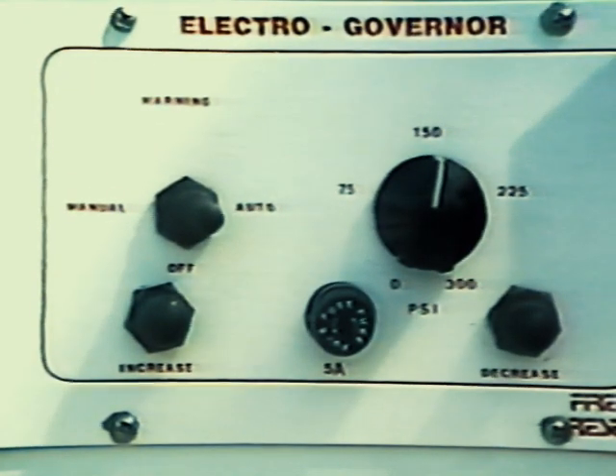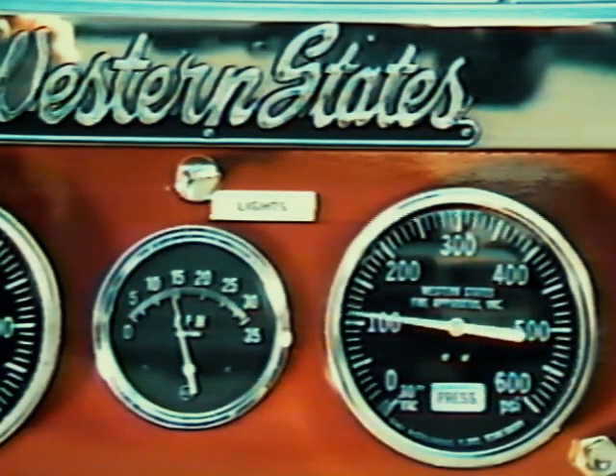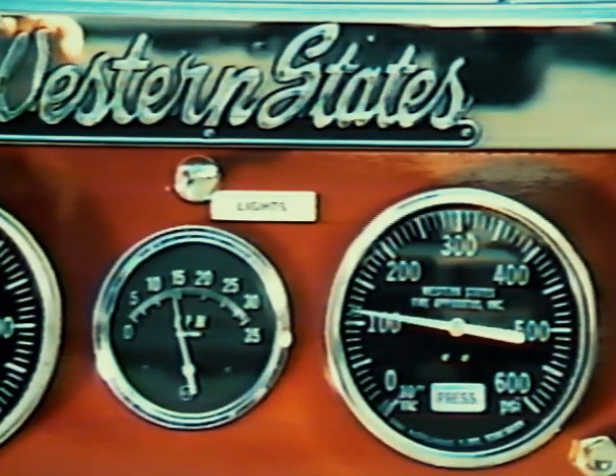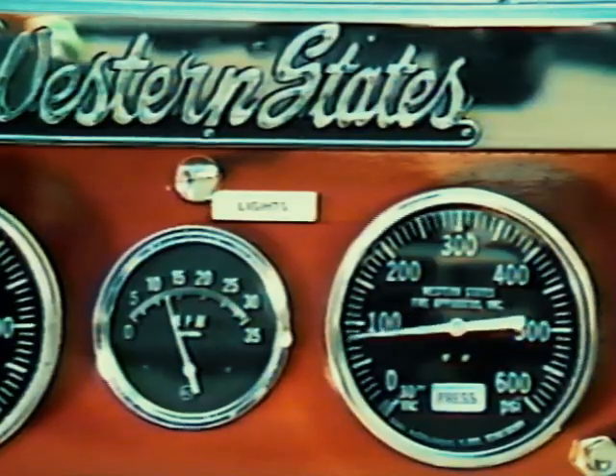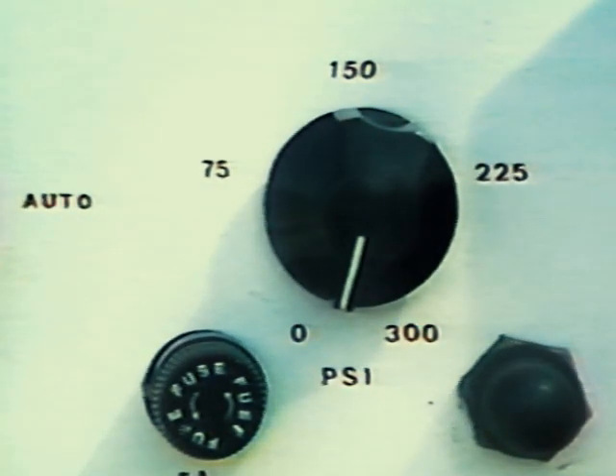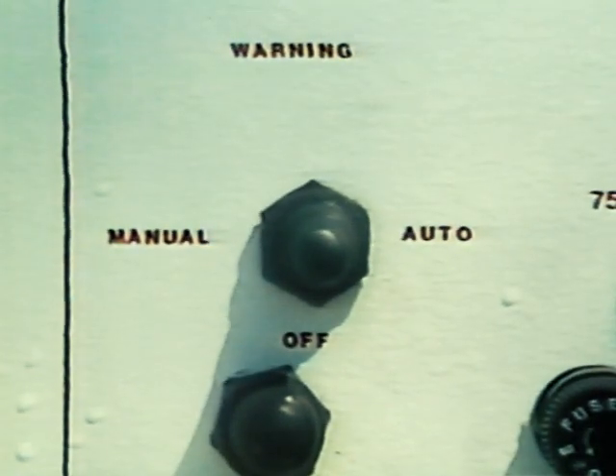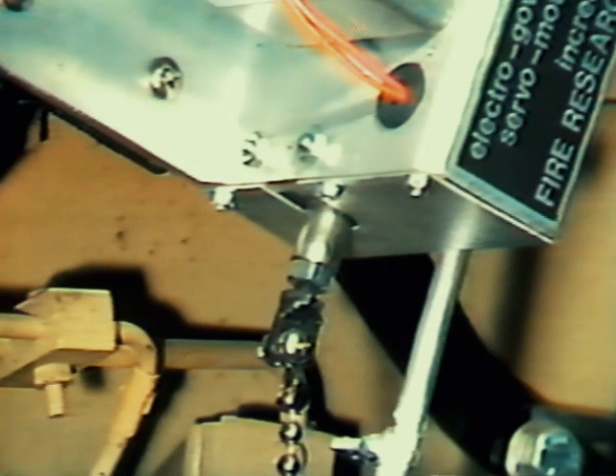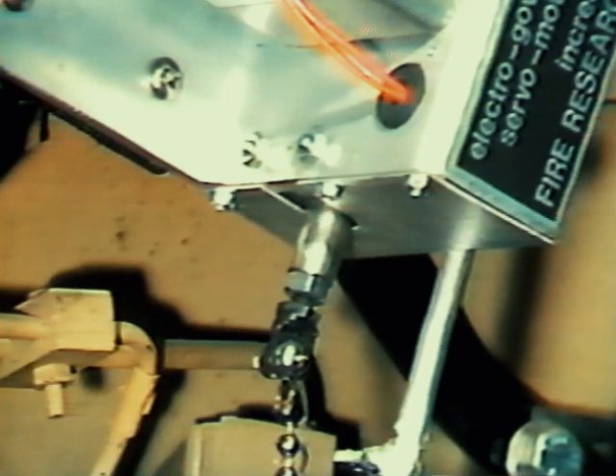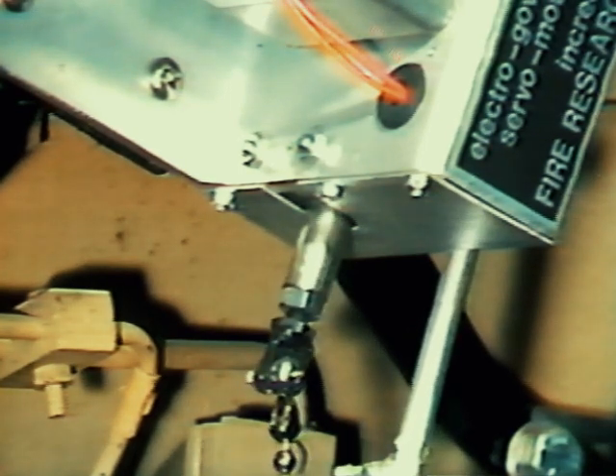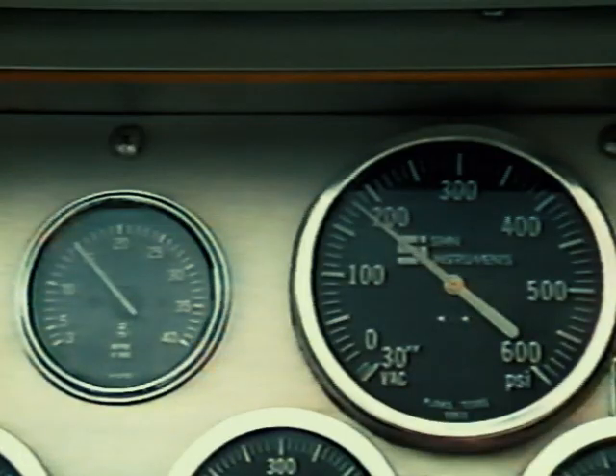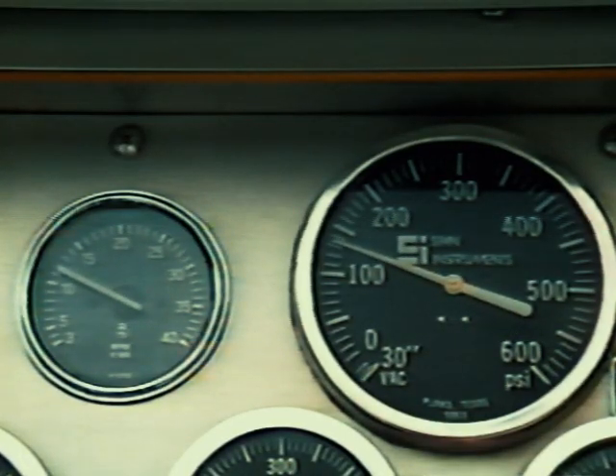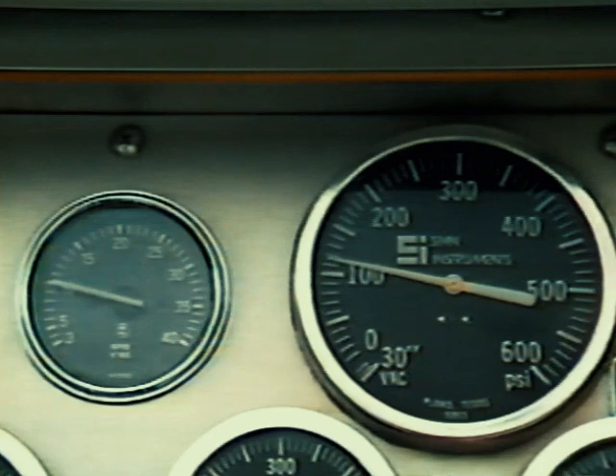A pressure governor works on the principle that a reduction of engine speed decreases the pump speed, which results in a reduction in water pressure. The controls for a pressure control governor usually include a pressure control knob and an actuator or control valve. The linkage of a pressure control governor is connected to the throttle of the engine. When the actuator is engaged, the system responds to excessive pressure by moving the linkage and slowing the engine down, which slows the pump and reduces excessive water pressure in the pump and hose lines.